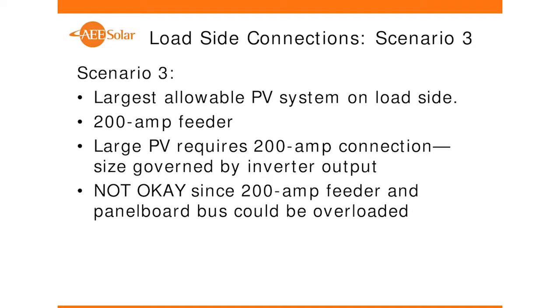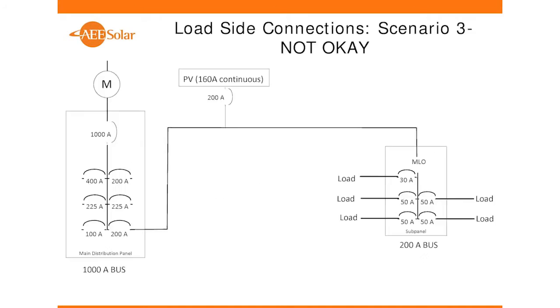Okay, so let's look at this particular scenario. If you had a 200 amp panel on a 200 amp feeder, you couldn't just interject it in the middle here because, as we said, you could start loading up this main lug only panel, and essentially the PV breaker, the PV system, could mask the main breaker from tripping. Any arguments to be made to a utility or jurisdiction saying commercial, that you can only make the connection at the main panel or near there because they want a PV production meter right next to the main panel? Yeah, there could be all kinds of other reasons, but when you're talking about a PV production meter, why does it matter where it is?